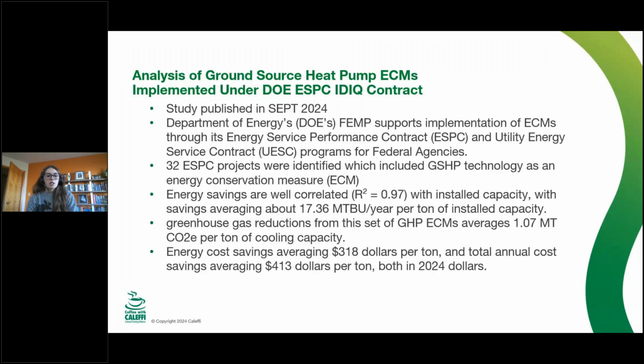They found 32 ESPC projects that included ground source heat pump technology as an energy conservation measure, and also looked at performance and cost metrics. Energy savings were well correlated with installed capacity, which I thought was interesting - a good rule of thumb for talking about ground source heat pumps going forward. Energy cost savings averaged about $318 per ton, and total annual cost savings averaged about $413 per ton. This is publicly available, and I'm happy to share it with anyone interested.